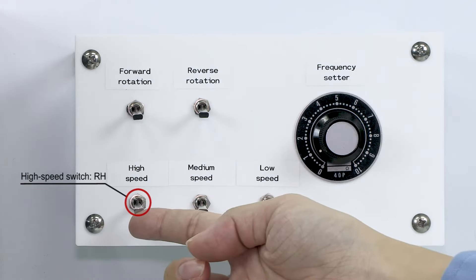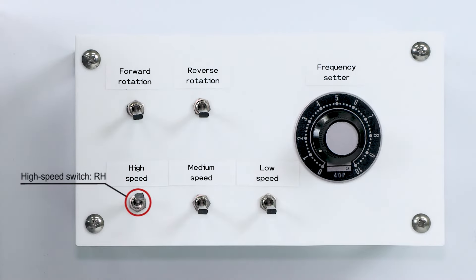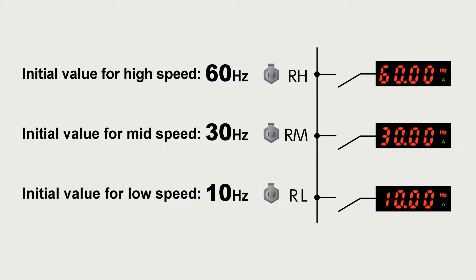Turn the RH switch on for high-speed operation. The initial value for the high-speed RH terminal is 60 Hz, 30 Hz for the mid-speed RM terminal, and 10 Hz for the low-speed RL terminal.